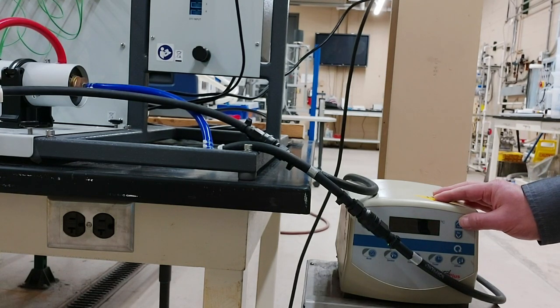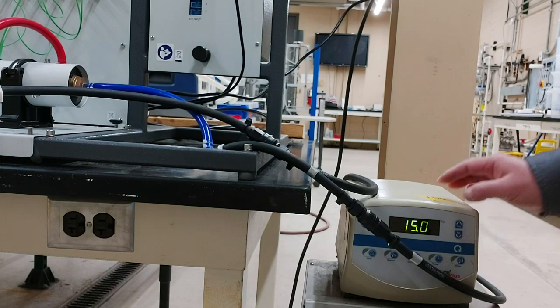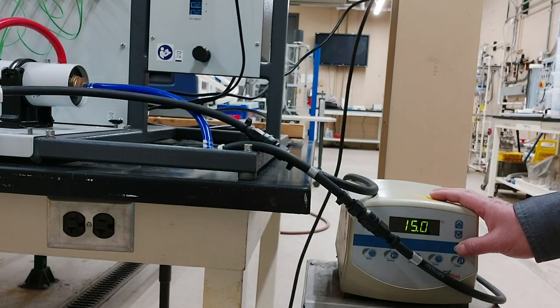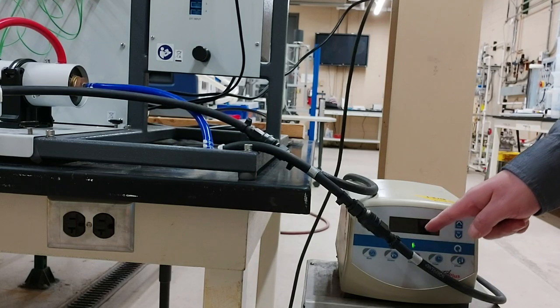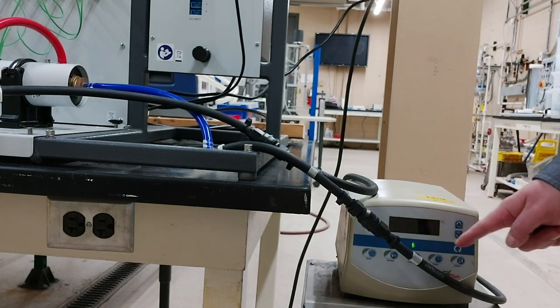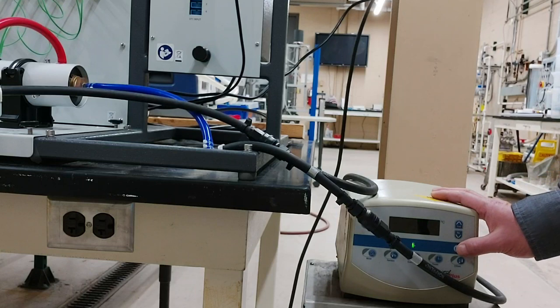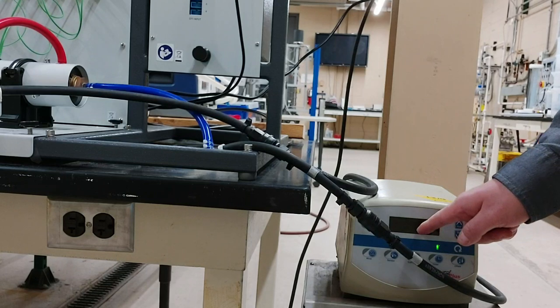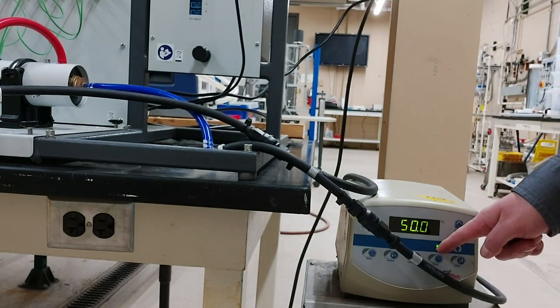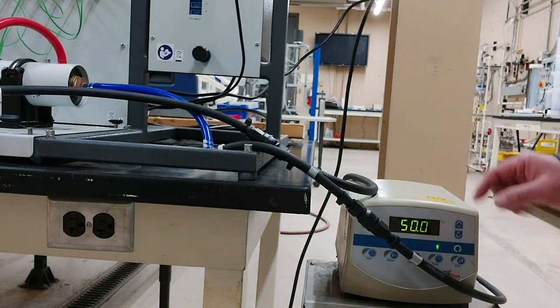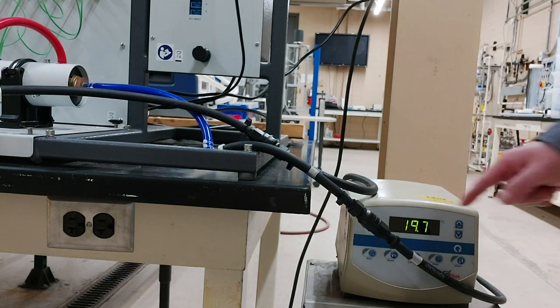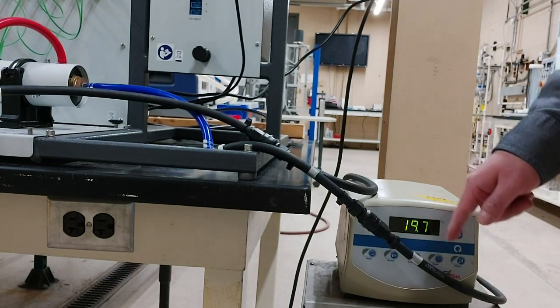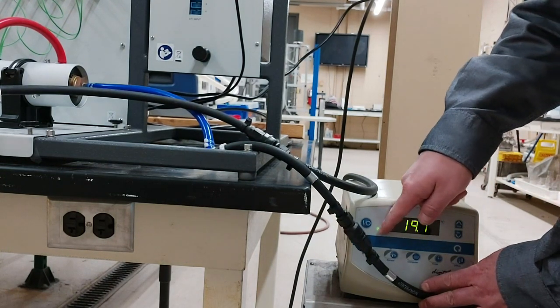If the set point is incorrect, you can change it by pushing the up and then down arrow button. If you push the circular arrow button again, you will see the low temperature limit below which you will hear alarm beeping. It's currently set as 10 degrees Celsius. If you push the circular arrow button once again, you will see the high temperature limit above which you will hear alarm beeping. It's currently set as 50 degrees Celsius. Finally, if you push the circular arrow button once again, you will go back to the current temperature display.